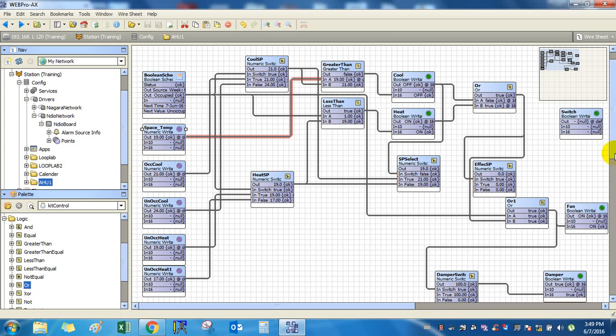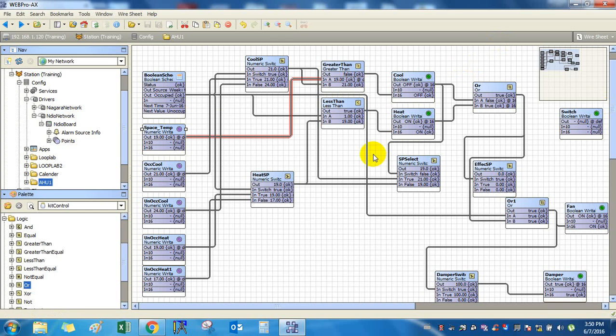Any questions here on this lab which we do? How did you finish? Okay. So look at this logic. We have 4 set points: occupied cooling, unoccupied cooling, occupied heating, unoccupied heating. So when we choose here, we still get 2. Output at this stage is 2 set points. Now based on these 2 set points, I am deciding whether I have to cool or heat. Correct? But when I am trying to cool or heat, I need only 1 set point.